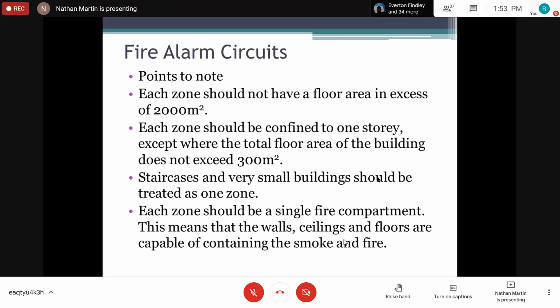So in a large building, the staircase is a zone, right? In a very small building, or a one-story building that is very small, a family dwelling is really one zone, right? Because typically you have those two entrances in most of these buildings, two doors, probably one main entrance and probably one fire. And normally the escape route is not labeled as an escape route. It's either your back door or the back door to the building and so forth, right?